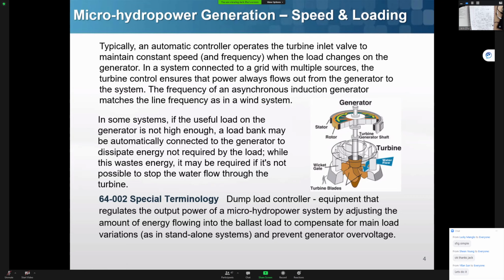And if you didn't use any of that power, you're going to cause something like over voltage or over frequency supplied to your house. So that's why you need to put a dump load down there. The dump load controller is required to match the output of your generator.